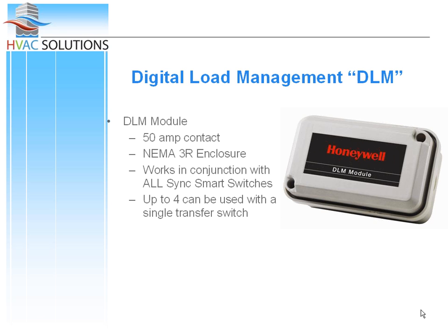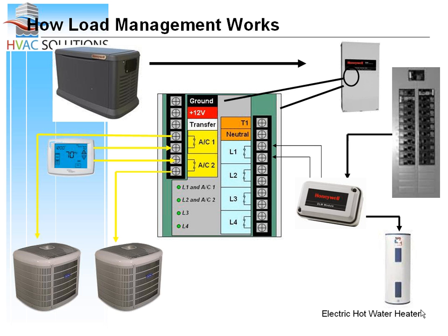This is the DLM, the Digital Load Management Control. All this is a 50 amp contactor in a nice little NEMA 3 box. So I like to call it the expensive contactor. This guy's, I'm going to say about 35 bucks, something like that. And I'm going to go back here because we use this DLM on the L side. So on any 240 volt load that we're going to shed, we have to have a 50 amp contactor between the circuit breaker and L1, L2, L3, or L4.